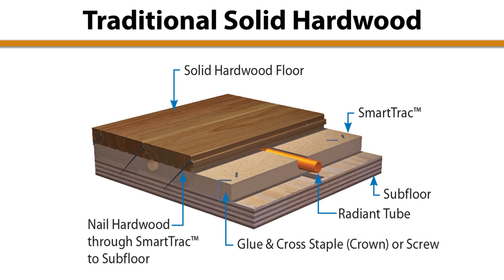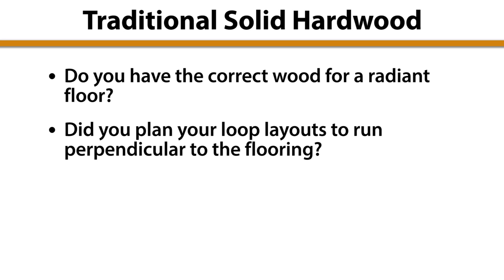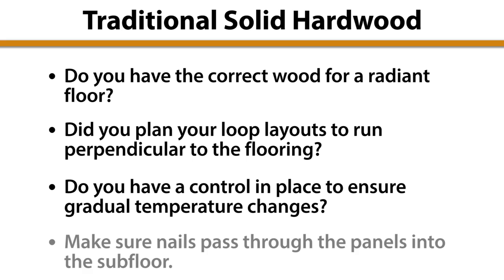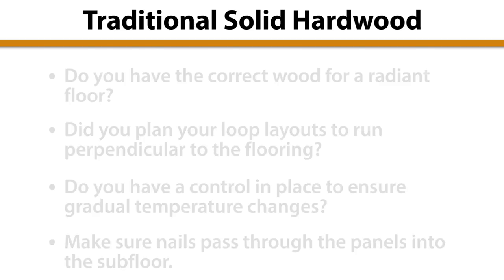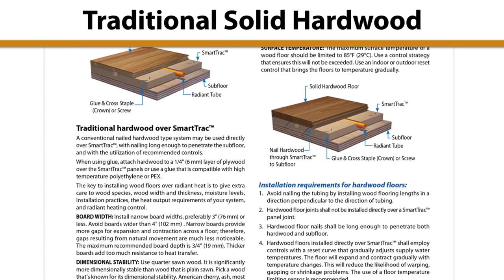Traditional installation of solid hardwood can be done with some precautions. Is the wood dimensionally stable enough for installation over a radiant floor? Have you planned the loop layout so that the lengthwise runs of tubing can be perpendicular to the flooring? Is there control in place to ensure supply water temperature changes are gradual? When installing hardwood, nails should pass through the SmartTrac panels into the subfloor. Read the additional precautions for direct installation of hardwood in the SmartTrac manual.